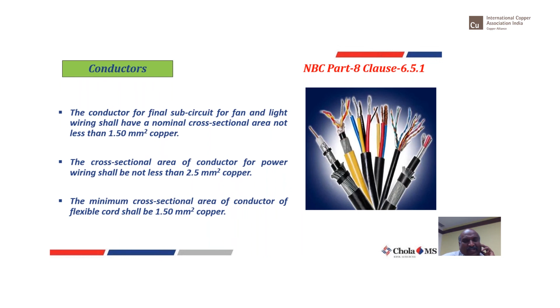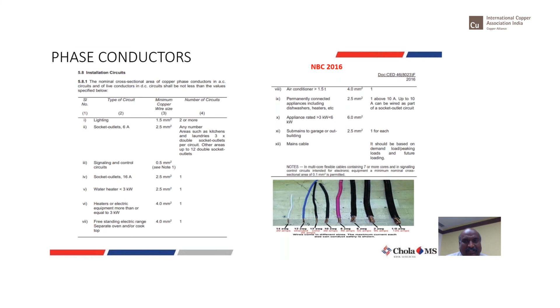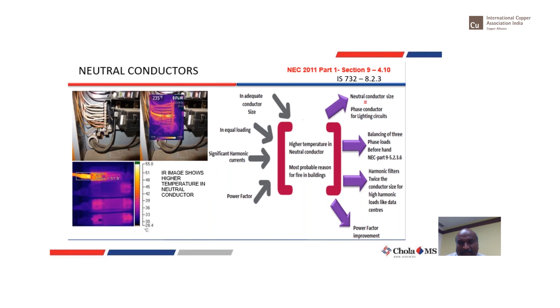This table also gives you clarity, as per NBC, for a lighting circuit or a power socket, what the cable sizing should be. I think the Copper team, Amul and his team, would be sharing these slides, and they would be available. You can use it for ready reference anytime. I'll be sharing these slides with them and you can take them from them, or they'll be putting them on their website where you can have access to it. So go with the right sizing, which NBC also talks about. Do thermal imaging and preventive maintenance on the electrical circuit so that you don't have any trouble from them.